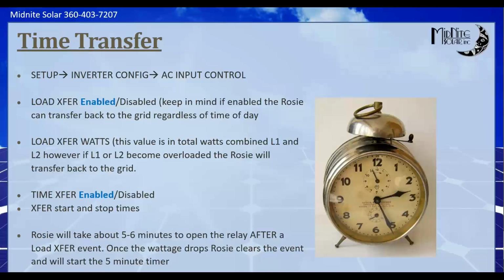And all these numbers, as we go through here, like the load transfer wattage or the charger amperage, when you see an actual value in the Rosie, like charger amperage or breaker size or load watts, that's per Rosie. So if you've got 4 Rosies in the system and you set load transfer for 7,000 watts, that's 7,000 watts times 4 is what it needs to see before it transfers back over to the grid. So just keep that in mind. But once you enable load transfer, it automatically enables the reconnect to the grid on overload of either leg. So if you overload one leg of Rosie, it will automatically reconnect to the grid.